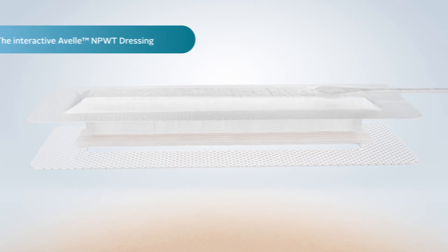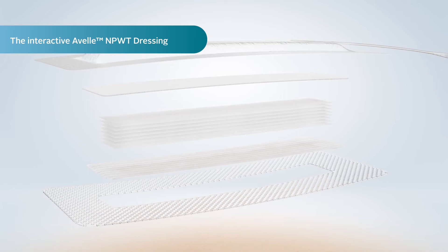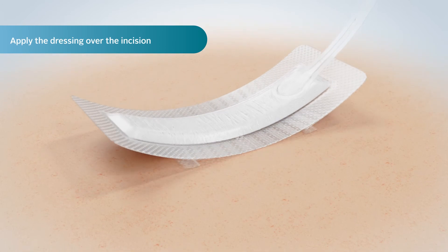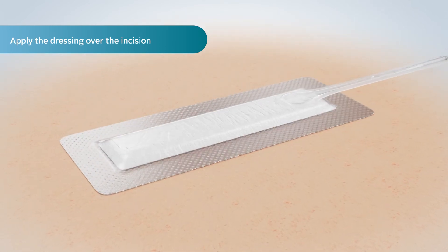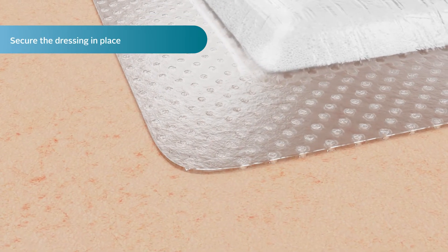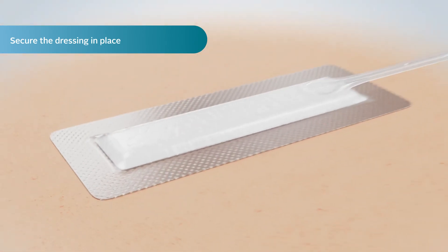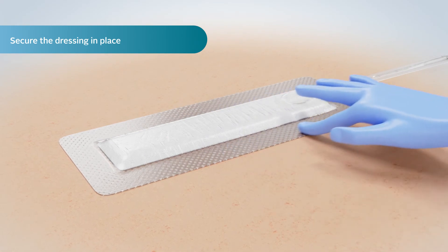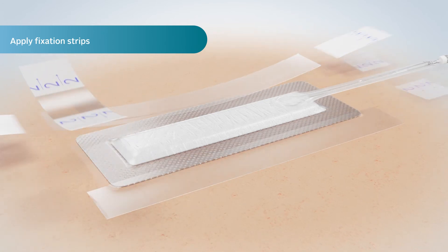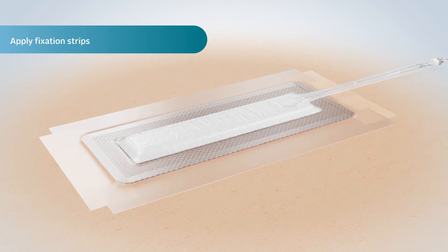The interactive Avelle dressing includes a Hydrofibre Technology Interface, which has many clinical benefits and has been engineered to deliver negative pressure to the wound. On application, the Avelle dressing should be positioned with the port over intact skin and uppermost from the incision. The perforated silicone adhesive borders secure the dressing in place while being gentle to the skin during removal. Ensure the border is smoothed out to minimise air leaks. Fixation strips can be applied with a 1 cm overlap to all sides of the dressing in order to maintain the seal during the wear time of the dressing.